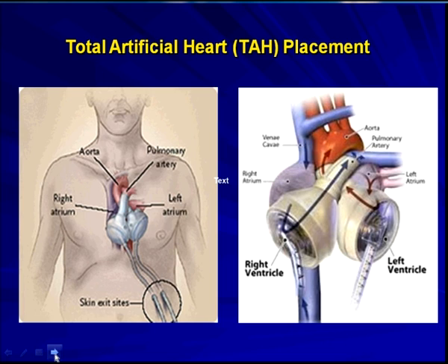Then we have what's considered the total artificial heart device by Syncardia. This is a whole other concept. Instead of augmenting the left ventricle, it actually just takes out the native ventricles and the native valves and replaces them with man-made mechanical chambers and valves. This, too, is a pneumatic-driven system, which is different than your continuous flow devices. Usually anything that's pneumatically driven is audibly louder than devices that are continuous flow. So you can actually hear this device working outside the human body without using a stethoscope.